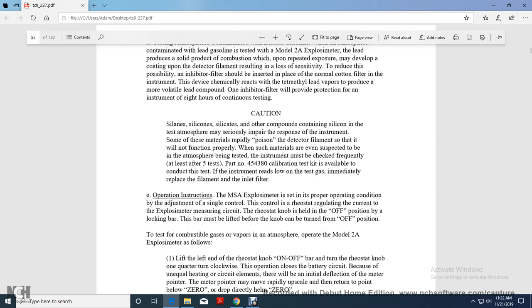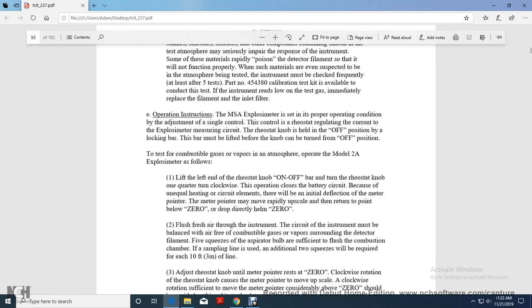Part number 454380 calibration test is available to conduct tests. If an instrument reads low with the test gas, immediately replace the filament and the filter.